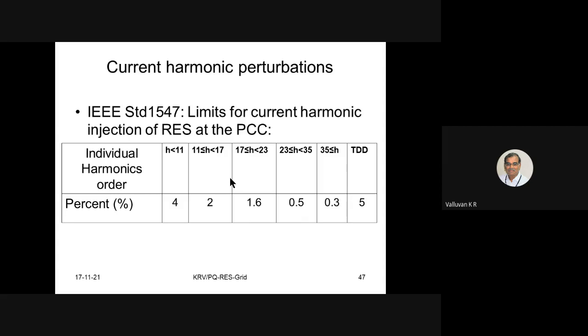Why is this happening? The photovoltaic cell produces DC, while the grid is predominantly AC. The DC produced by the photovoltaic cell has to be converted into AC and then injected into the grid. When we invert DC into AC using power electronic equipment, that produces harmonics. That is where the issue is. If we run a conventional generator, or rather an alternator to be very specific, you can synchronize and control the amount of harmonics. Ideally, there should not be any harmonics, but we can have 0.1% or 0.2%, which can be controlled. But solid state power electronic inverters produce harmonics which are to be limited within 5%.